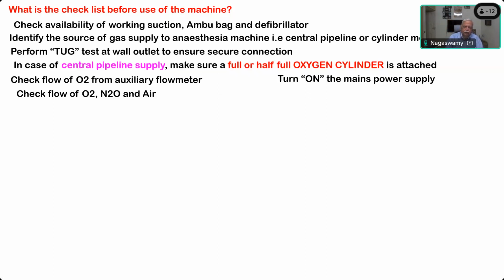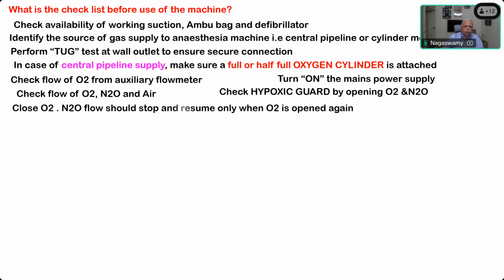So by just opening the nitrous oxide, you cannot expect oxygen to flow unless you open the knob of the oxygen. The correct method of checking the hypoxic guard is to open oxygen and open nitrous oxide to equal flow, close the oxygen and see whether the nitrous oxide bobbin drops to 0 immediately. And once you reopen the oxygen, nitrous oxide will automatically rise to the previous level that you had kept. That is how the hypoxic guard is tested. First, open both oxygen and nitrous oxide. Then close oxygen; nitrous flow should stop and resume only when oxygen is opened again.